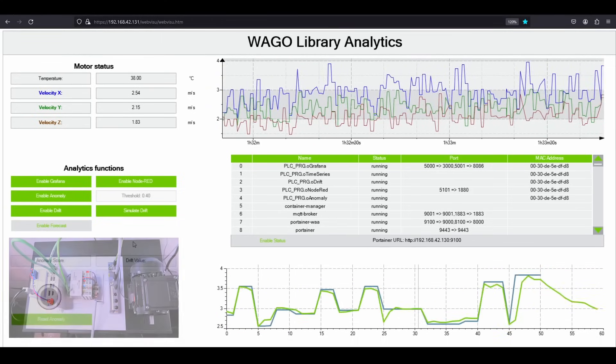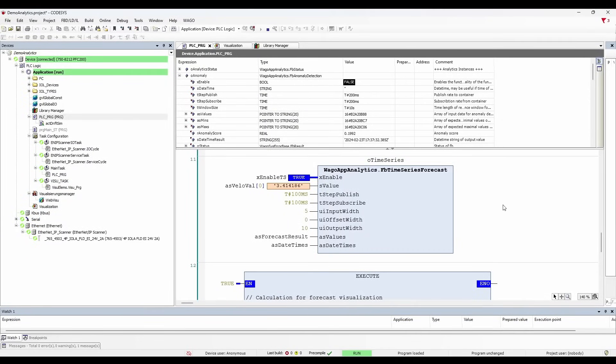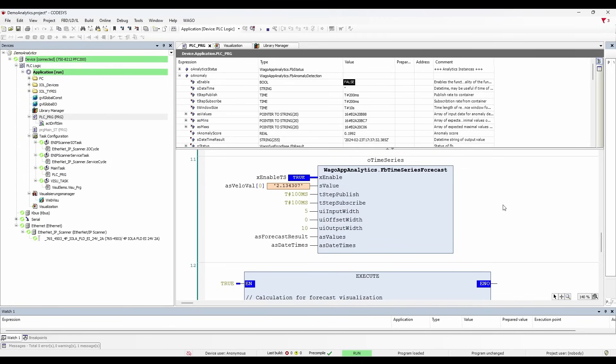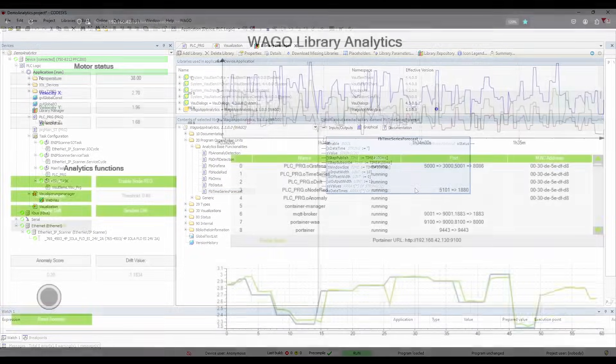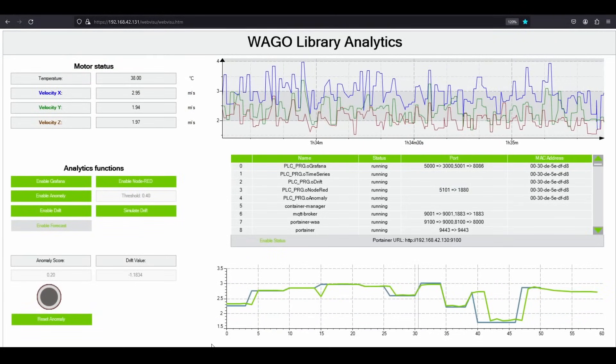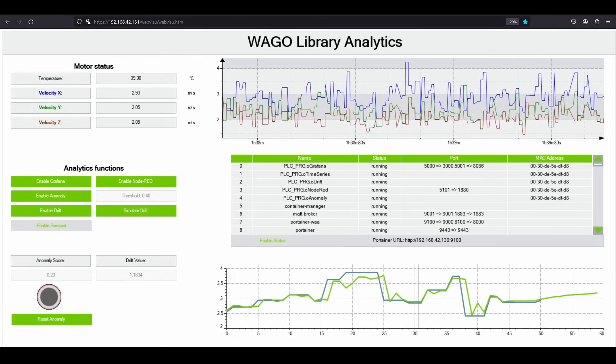This is achieved using the time series function block, which starts the specific Docker container on the edge device. So in the PLC program, I'm sending only the velocity RMS for the x-axis with my default publishing and subscription time. The input width is 5, which is the number of data points used to make a prediction. The output width is 10, which defines the number of data points predicted. Thus, 5 data points are used to predict 10 data points in the future. After analysis, the function block returns the predictions as an array with the associated timestamp. More information about this functional block parameters can be found in the documentation. So you can imagine how you can easily schedule your upcoming maintenance.